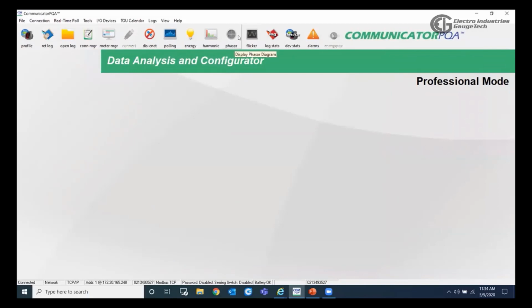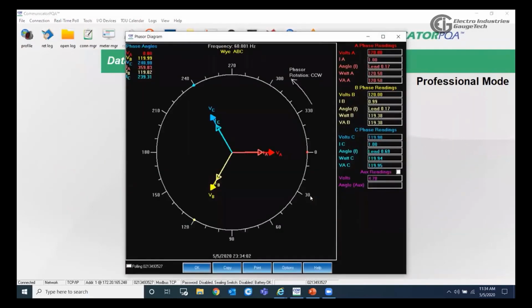Then we have the phasor. This is a nice function to help if there is any wiring issue and we need to troubleshoot that. So the phasor diagram can tell us what's exactly wrong with the wiring. When we're looking at the phasor, we are looking for something similar to this. We have the three voltages, 120 degrees apart, and we have the current of each phase lagging or leading the voltage by a small angle.